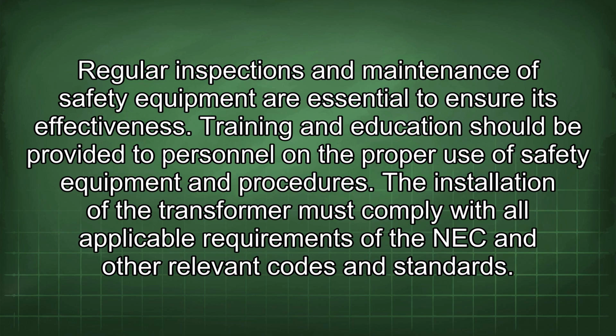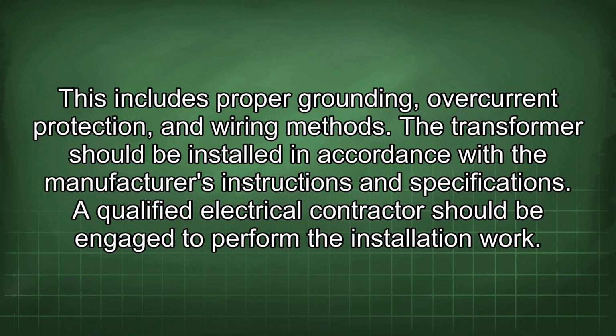Training and education should be provided to personnel on the proper use of safety equipment and procedures. The installation of the transformer must comply with all applicable requirements of the NEC and other relevant codes and standards. This includes proper grounding, overcurrent protection, and wiring methods. The transformer should be installed in accordance with the manufacturer's instructions and specifications. A qualified electrical contractor should be engaged to perform the installation work.